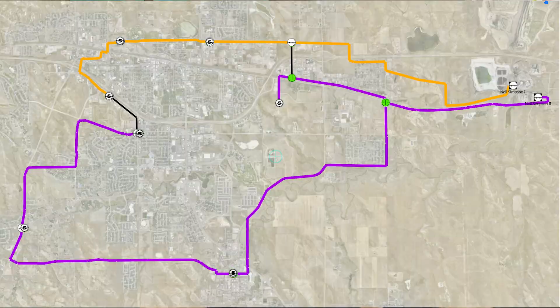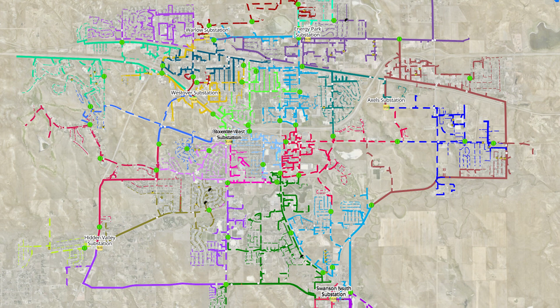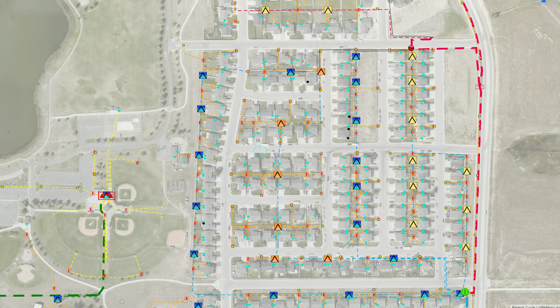We run a looped system on our transmission line, meaning we can feed the town from either one direction or the other. If we have a problem on the south loop, we can tie it to the north loop to maintain consistent power. This is a very intricate system that spider webs throughout the city, providing power to all the homes. We can tie one feeder to another feeder, turn this feeder on and that one off, move large amounts of power every day, and take power down to one substation for maintenance or load balancing. All of this is done without the citizens even knowing.